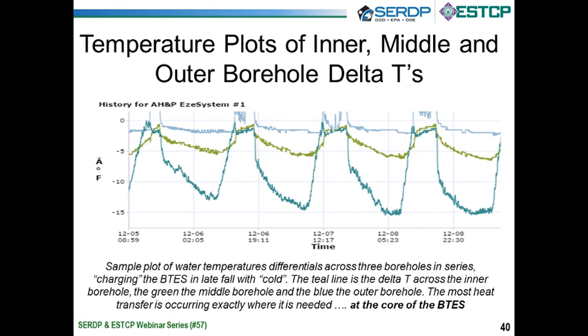Then with less delta T available, less LMTD between the ground and the water, our middle borehole gives us, what do you see there on the green line? Maybe a 5 to 6, 7 degree delta T. And then the outer borehole, yes, we're only getting a 2 to 3 degree delta T. But in the military analogy here, there is an infinite regiment of soldiers surrounding this BTES, all at 70 degrees, trying to come forward and destroy all our efforts to make cold. So we don't want to give them attractive targets at the perimeter. So we're only going to let that perimeter be a couple of degrees colder. But the neat part is when you add up the 15 degree delta T plus the 6 degree delta T, you're at 21, a couple more. Maybe you're getting a 23 degree delta T.